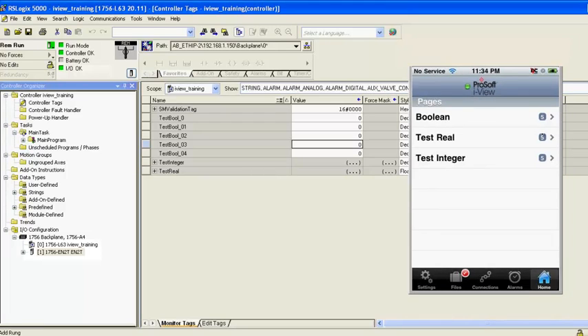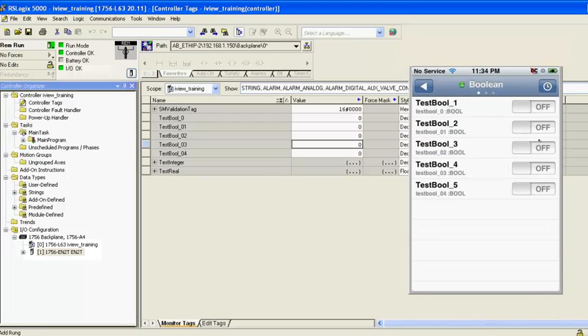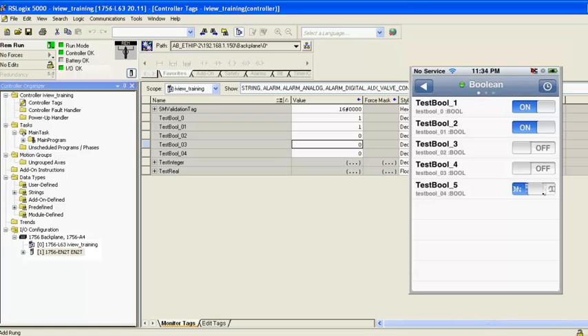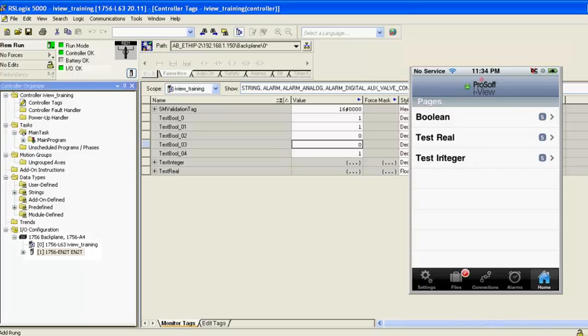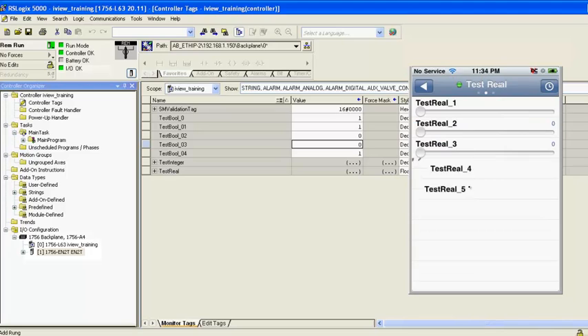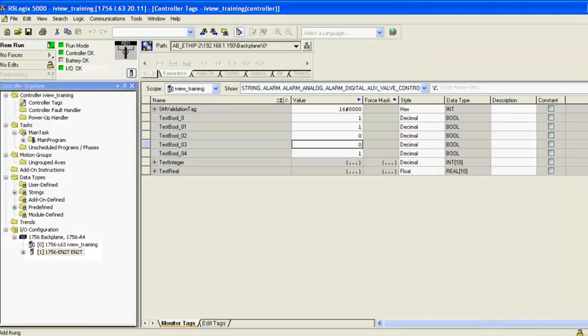I'll tap on the Home button. At the Home screen, I can see the three pages that I created in iView Configurator. I'll open the Boolean page and set some tags to On. Back in RSLogix, I should see the corresponding tags set to 1.